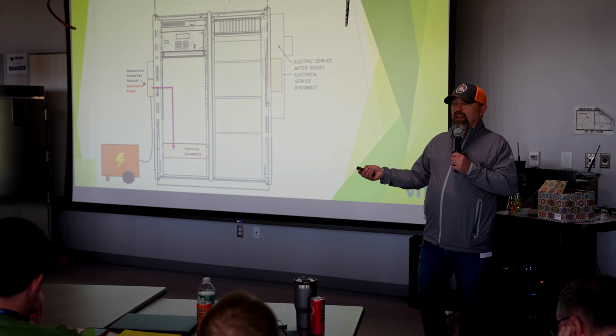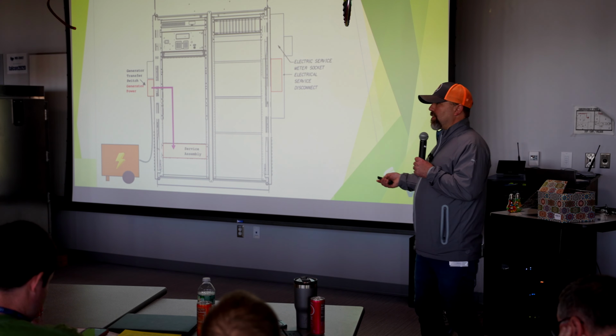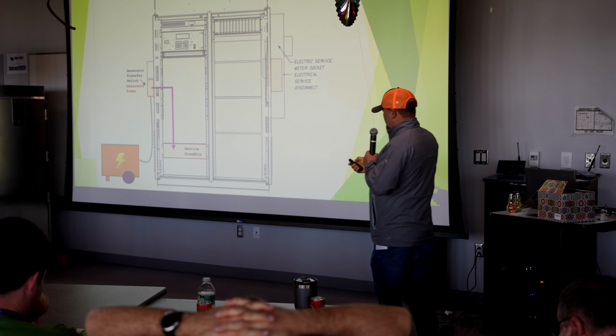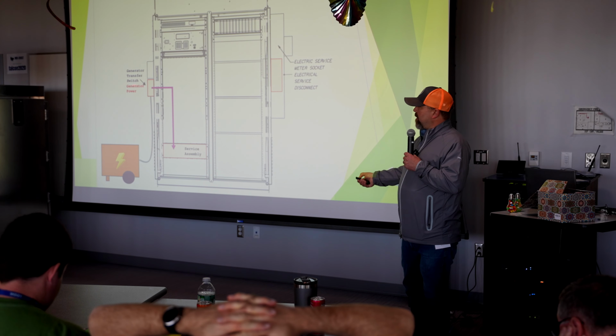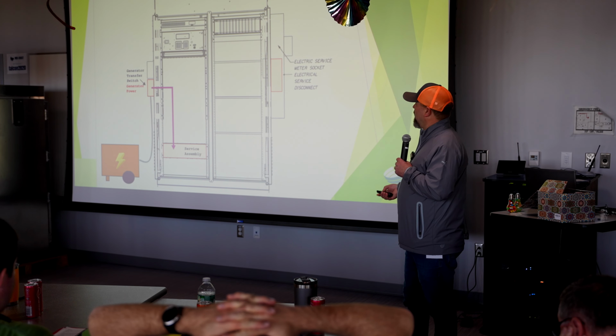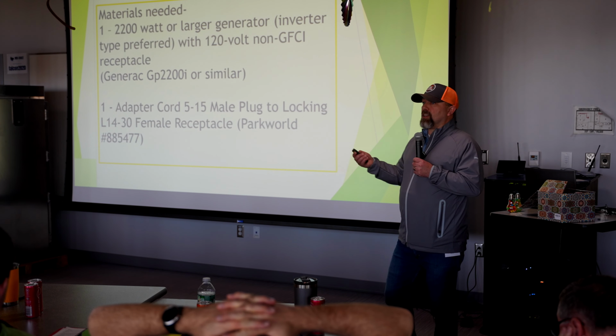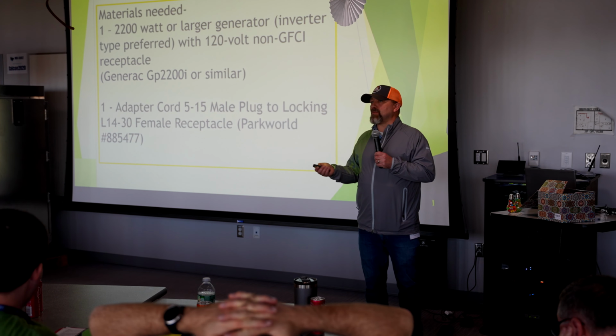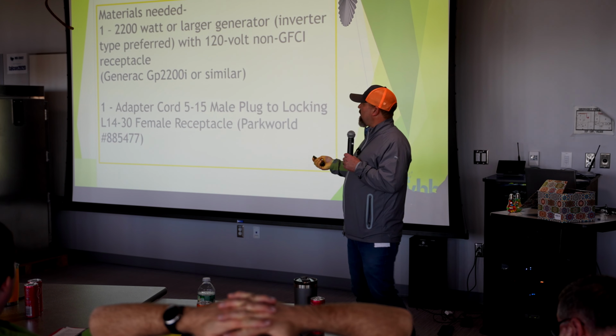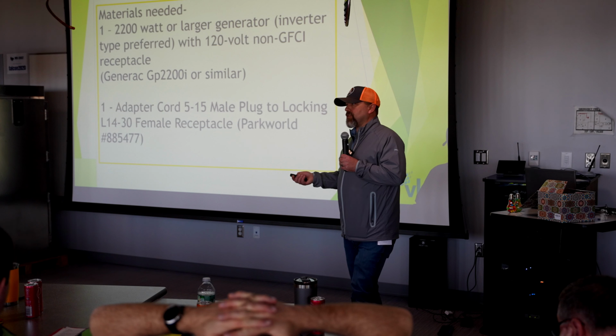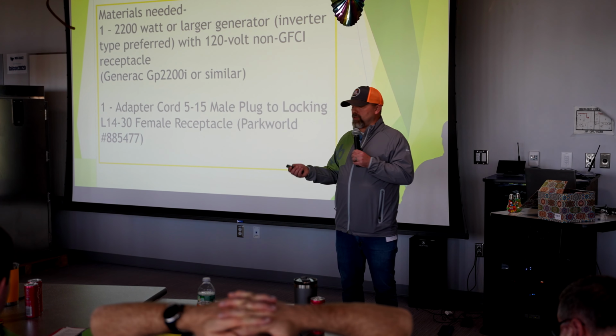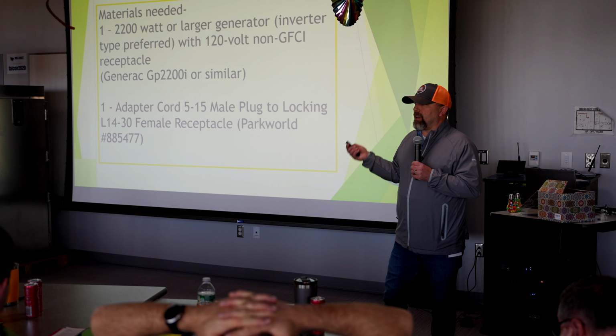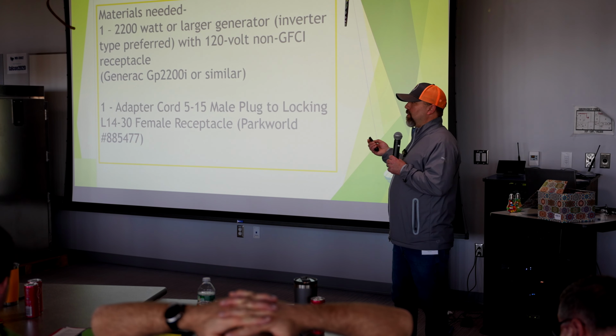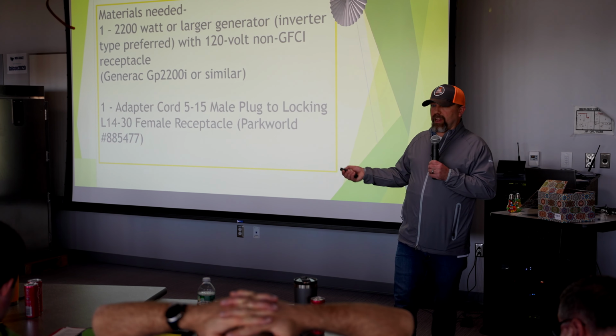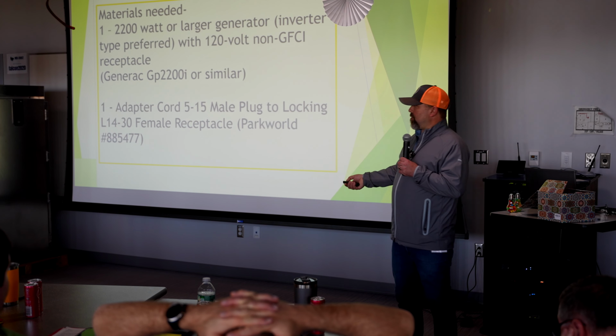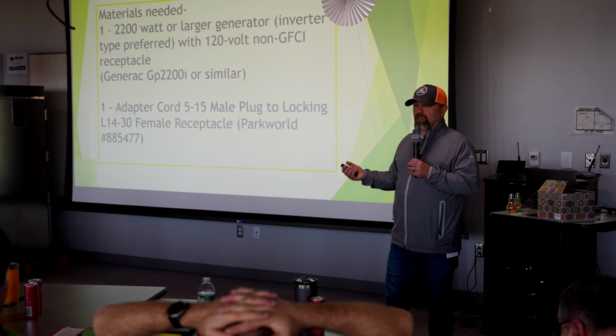Then obviously when you're on generator power, I'll show you the sequence or the procedure for transferring it. But at this point, when you're on generator power, you're just feeding into the manual transfer switch to the service assembly. I've been asked this a couple of times now. The transfer switch that was used on this is a 4-wire transfer switch, so technically it's a 240 volt transfer switch. These cabinets only run on 110 volts. Even though the transfer switch is rated for 30 amps and you have a 30 amp main breaker, typically these cabinets draw about 600 watts, if that.